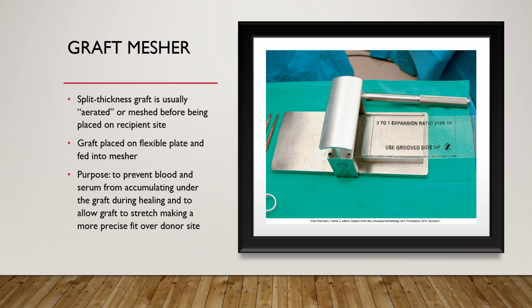Okay, once we have our skin graft, it is going to usually be put through a graft mesher. Usually this is with the split thickness graft. It needs to be aerated or meshed before being placed on that recipient site. The graft's placed on a flexible plate and fed into the mesher. And this is our flexible plate here. We would lay our graft down on it, and then we would navigate this handle back and forth. And what that's going to do is feed this plate through and cut diamond-shaped holes into that tissue and cause it to come out with a mesh kind of appearance.